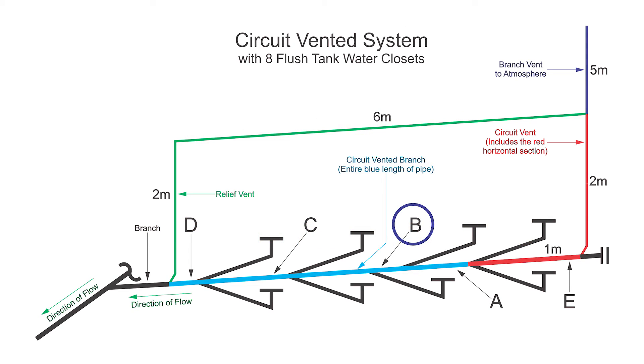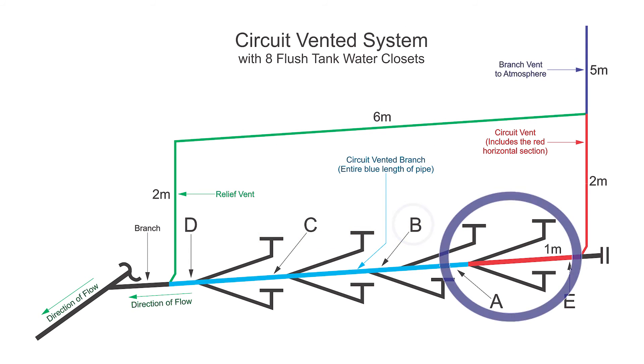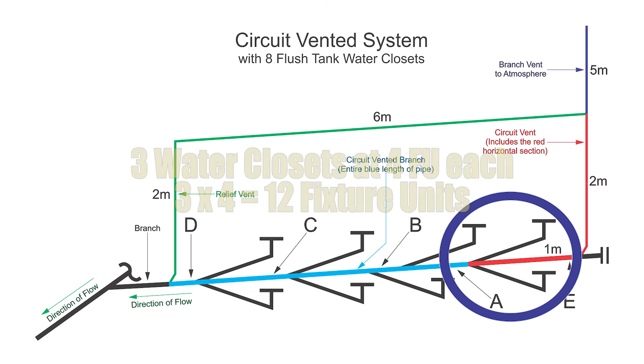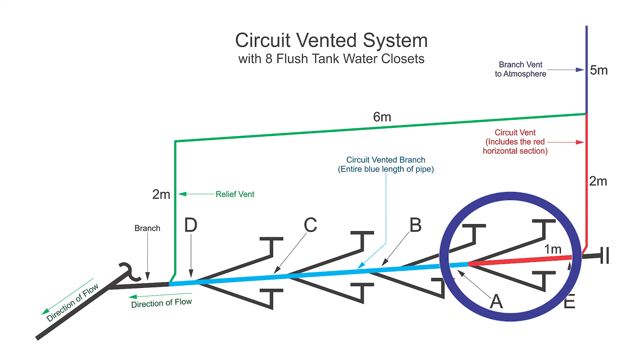Now let's look at pipe B. Pipe B is downstream of 3 water closets, so 3 times 4 is 12 fixture units. It still needs to be a minimum of 3 inches because of the size of the fixture outlet pipe for the water closet.